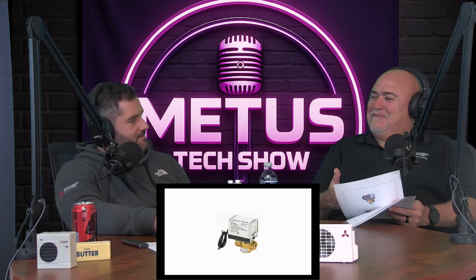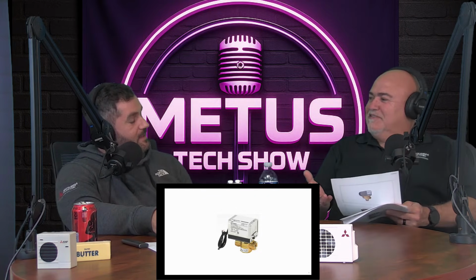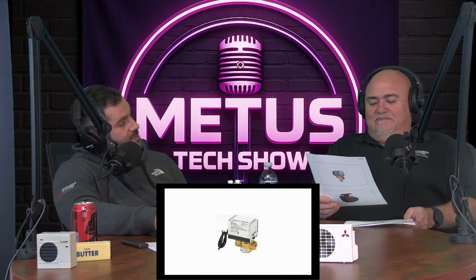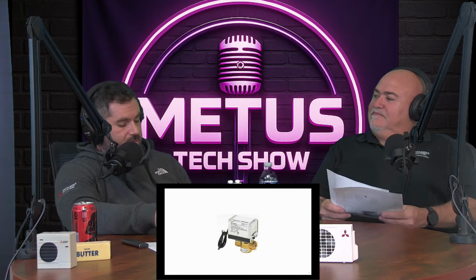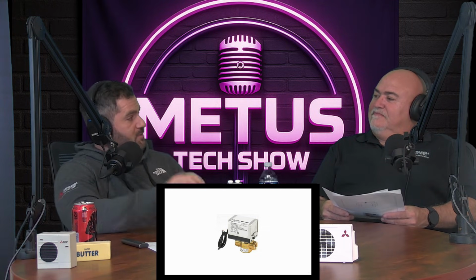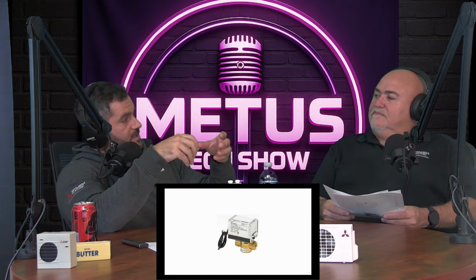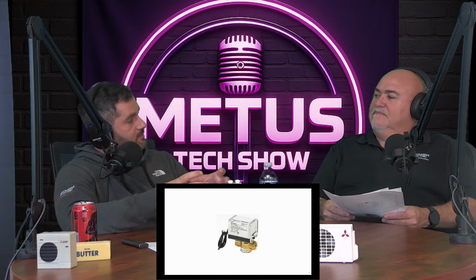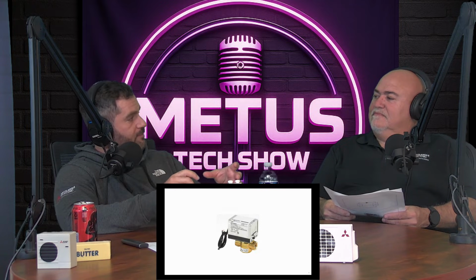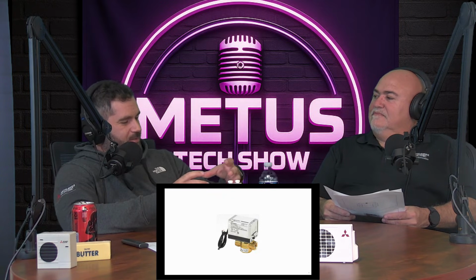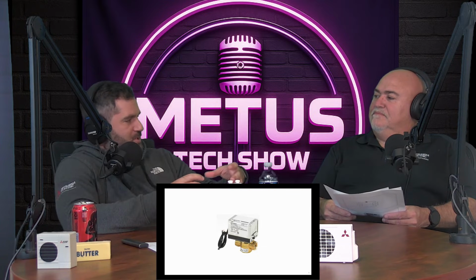This is probably one of your favorite valves. Yes, you expressed how much you love these things, because they're easy to service. Yeah, the valve is not tied to the head, the motor. So you can actually remove these pretty simply. You just pull on the manual valve and a little twist, and the whole thing just pops right off. So no screws have to come out. It's literally just held in with the manual valve and the manual lever, and it's almost like clipped in. So to release it, you just twist and pop.